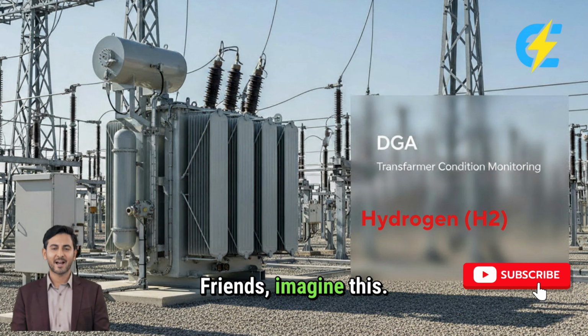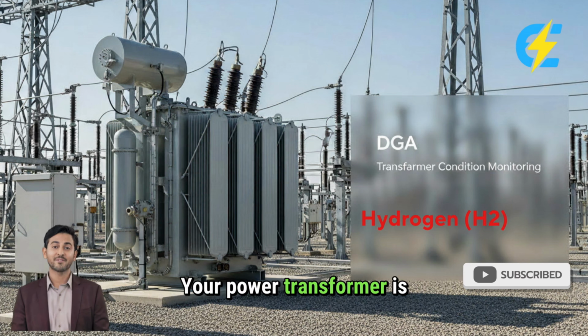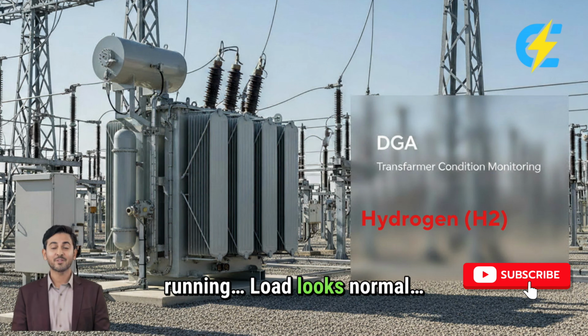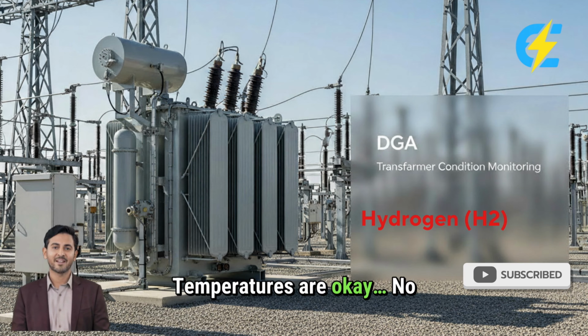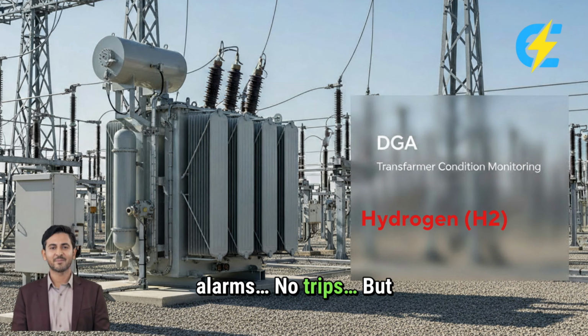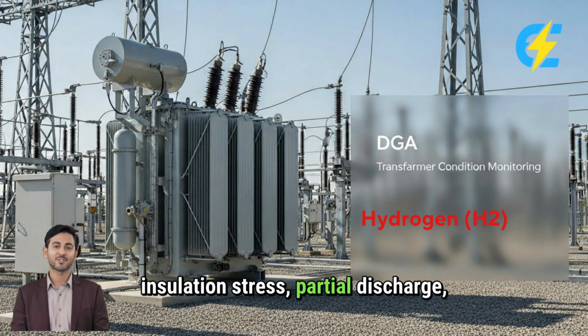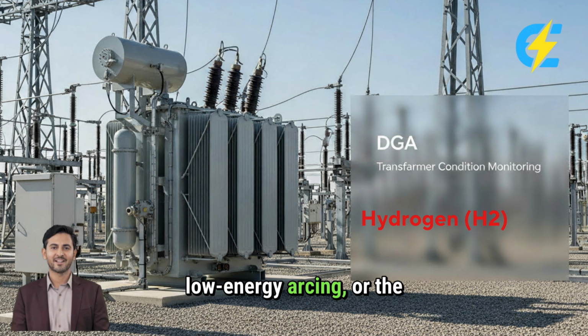Friends, imagine this. Your power transformer is running. Load looks normal. Temperatures are okay. No alarms, no trips. But inside the oil, hydrogen is silently increasing. No smoke, no fire, no visible fault. Yet this one gas alone can tell you insulation stress, partial discharge, low energy arcing, or the very first warning before a catastrophic failure.